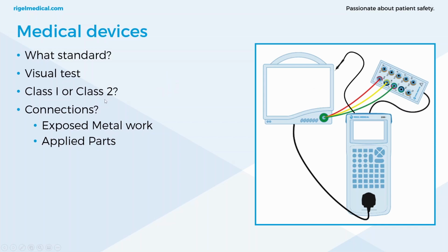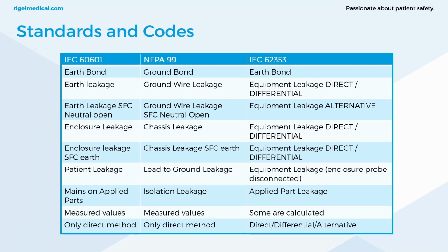You need to establish, is it Class 1 or Class 2? What connections does it have? Does it have any exposed metal work? What types are they? So is there B, BF or CF? A patient monitor, for example, will have multiple functions with different types of applied parts. Now, classification of applied parts is not actually relevant for NFPA 99. It does simplify the process. The applied part limits are the same. There's no different classification between whichever applied part you're testing. It's all identical. But if you're testing to 60601, then that's when the type of applied part becomes relevant.